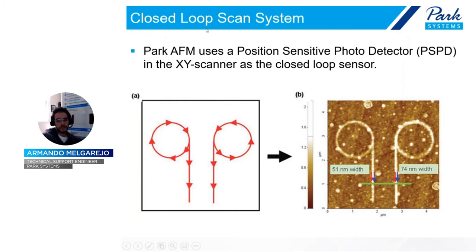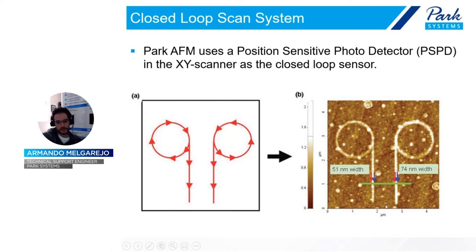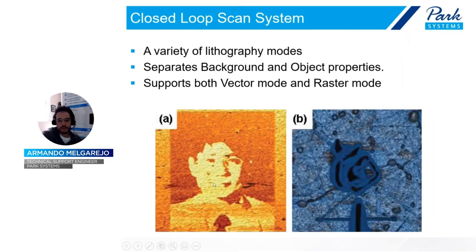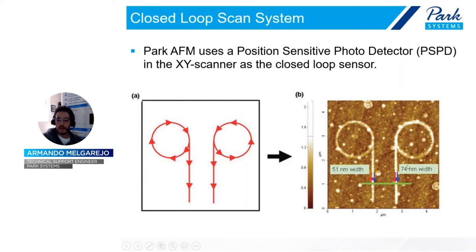Park Systems uses a closed-loop scan system. Specifically, Park Systems uses the PSPD photo detector in the X-Y scanner as the closed-loop sensor. This allows us to move in a vector movement instead of a raster movement. Normally, all AFM techniques work in a raster scan — scanning left to right across the entire image, including background — which takes longer. But when doing a nanolithography process using vector movement, we go directly to the desired feature, tracing just the circle, then the line, then the other circle. This vector movement is enabled thanks to the photo detector used as a closed-loop.